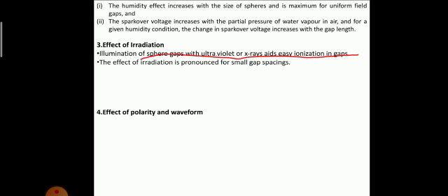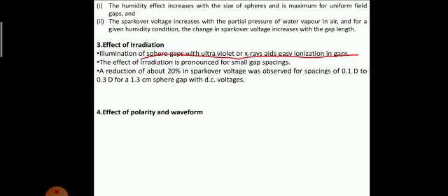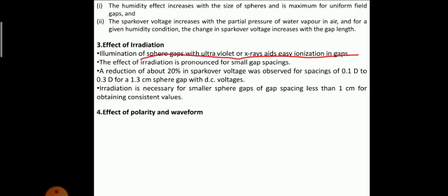The effect of irradiation is pronounced for small gap spacings. So this is good for small gap spacings. A reduction of about 20% in the spark over voltage was observed for spacings of 0.1 times D to 0.3 times D for a 1.3 centimeter sphere gap with DC voltages. Irradiation is necessary for smaller sphere gaps, with gap spacings less than 1 centimeter. So this irradiation is not used to initially ionize the gap if the gap spacing is large or the sphere diameter is more. It is only done for smaller sphere gaps and smaller gap lengths.